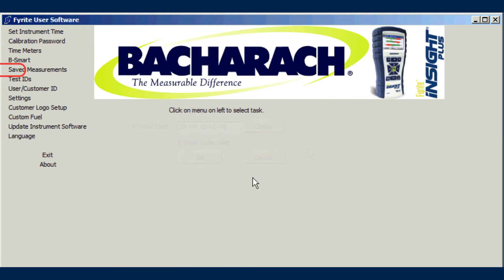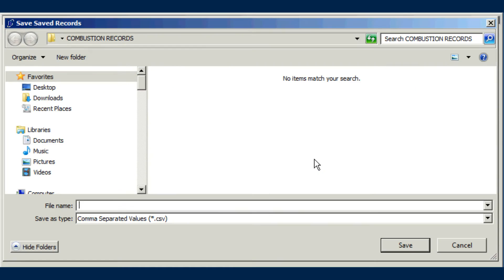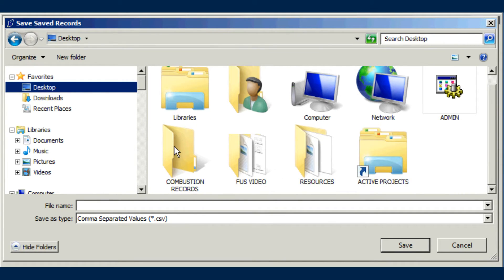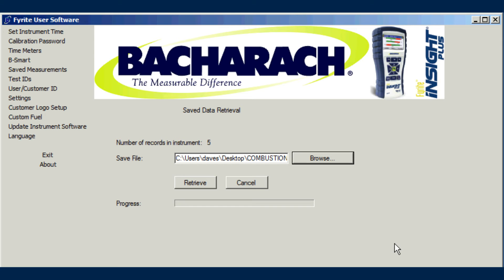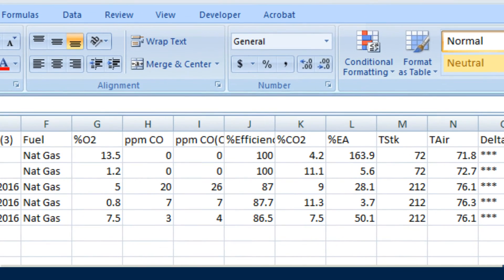For test data that the operator manually saves to the analyzer's memory, the Saved Measurements menu item retrieves all saved data records from your instrument to a CSV formatted file on your PC. The software will show you how many records are currently in the connected instrument. First, use the Browse button to locate a desired target directory on your computer. Next, enter a file name for the CSV data file and click Save. Finally, click the Retrieve button. Progress of the data transfer will be shown on the screen. Once the transfer is complete, you can read and evaluate the saved measurements using any software program that supports comma-separated variable format.